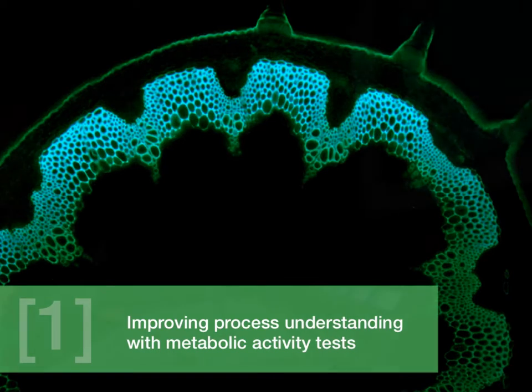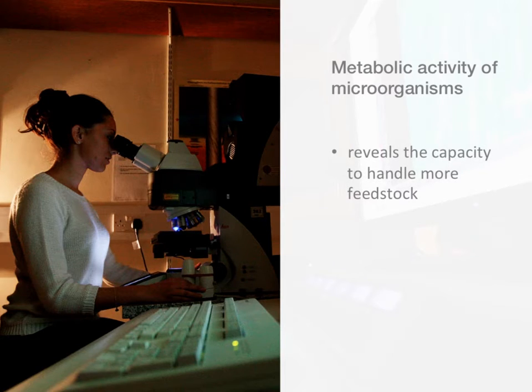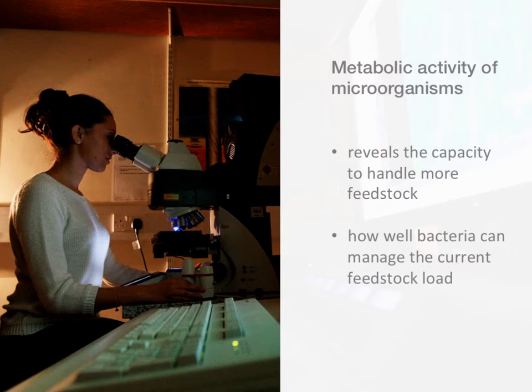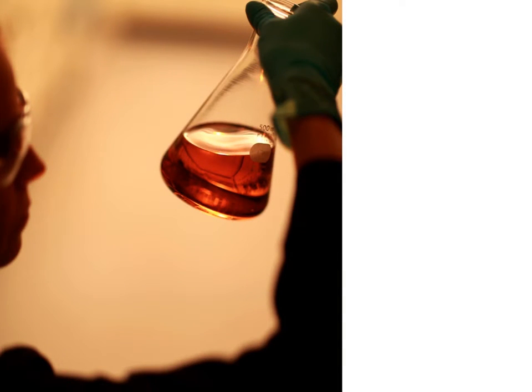Perhaps one of the most important aspects of the AD process is the metabolic activity of the microorganisms. Information about this parameter reveals the capacity of the process to handle more feedstock, or how well the bacteria involved will be able to manage the current feedstock load. Monitoring of this parameter is relatively rare in most biogas plants today, which severely limits the plant's ability to efficiently operate the process.